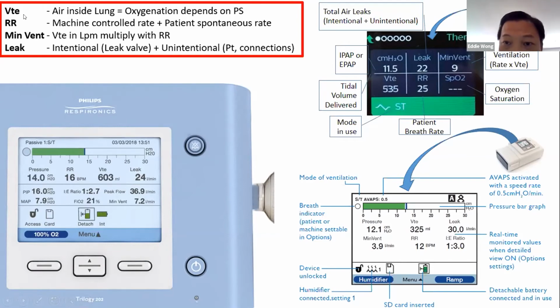Why do you need to know the actual tidal volume in each of these ventilators? Because how much air goes inside your lungs depends on the VTE. It is the volume of air recorded here, and you need to check with your doctor what the desired, optimum tidal volume is. Even though we are using pressure control ventilators, where we set the pressure and not the volume, you need to know what volume of air is enough to sustain our life and the oxygen level in the body. So that's why you need to learn to read this reading called VTE.